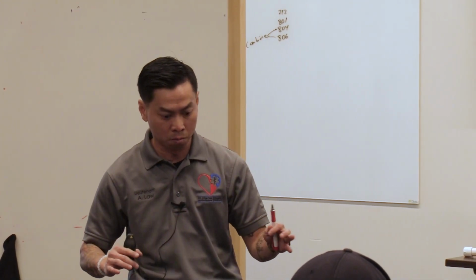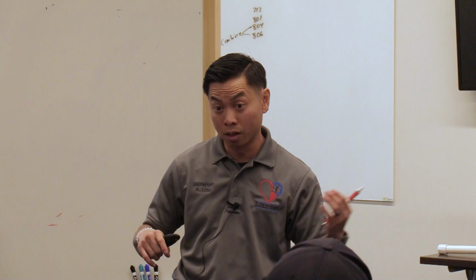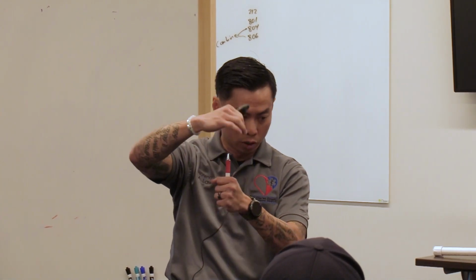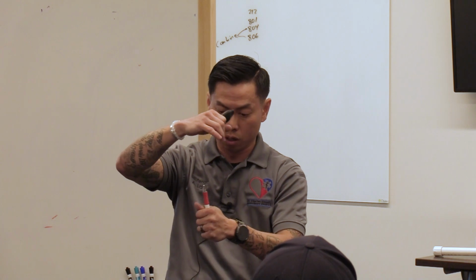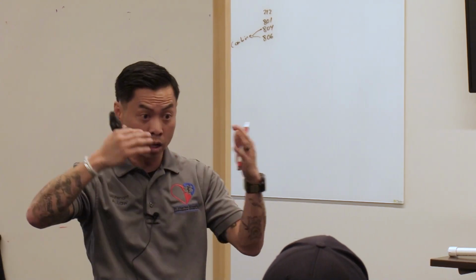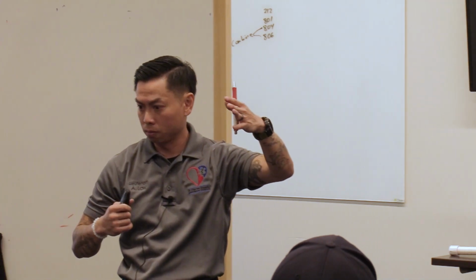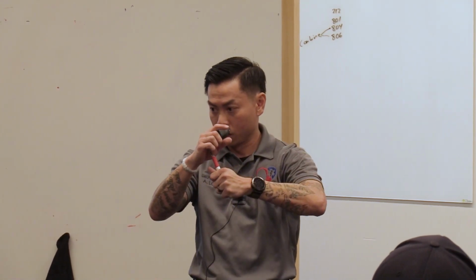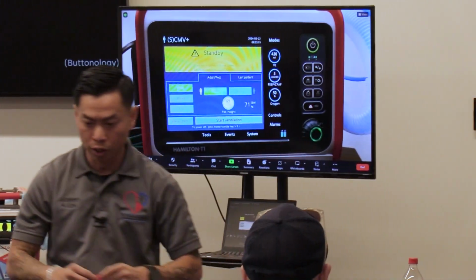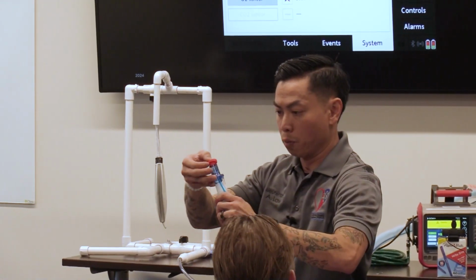So the leak test, it is purely that. It is testing for leaks in your system. In order to test for a leak, it's going to try to send air. You're going to put your hand over the circuit, and when it tells you and shows you, you'll put your hand over the circuit, and it tries to send air. You should not hear any air movement, right? Because if you do, then it's leaking somewhere. Pressure will build up, it'll pop off, and it'll say disconnect circuit from patient. That means just take your hand off. So when you first start it up, it's going to say disconnect circuit. And it gets kind of confusing because if you get a new circuit, this one will be at the end of this.